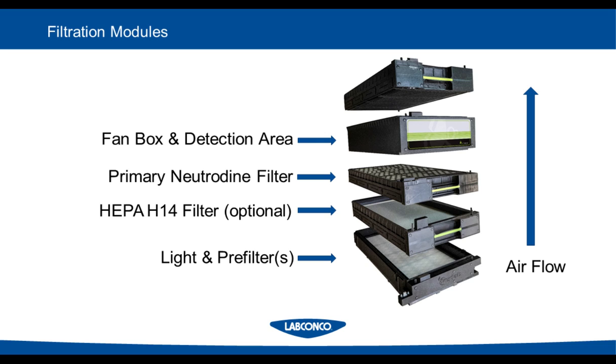This fan is drawing air in through the open sash, up through the cavity of the fume hood, capturing whatever is being evaporated, vapors and whatnot used inside that hood, and then drawing it up through the filtration column. So again, any leakage would be clean air into dirty, not contaminated air blowing out. This is a very important point, and of course we comply with that also.